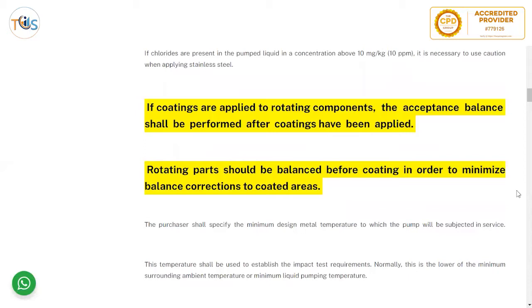If coatings are applied to rotating components, the acceptance balance shall be performed after the coating has been applied. Always apply coating after the pressure test of pressurized parts. Rotating parts shall be balanced before coating in order to minimize balance corrections to the coated areas, since coating adds thickness that can unbalance the impeller. It is better to balance the impeller first, then apply coating, and then do a fine-tuning residual balance.